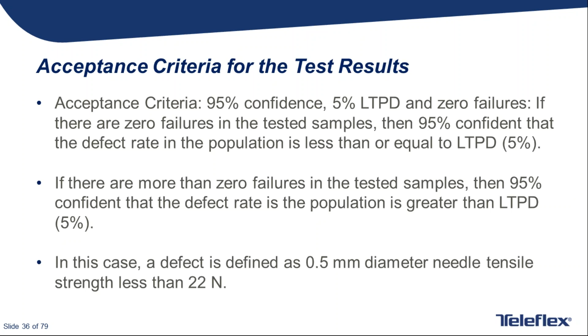So now we're going to turn to the same example, but apply variable testing to it. So it's going to be a little more complicated. For variable testing, we need the same items as for attribute testing, with the addition of power and difference to detect. Acceptance criteria should, of course, be determined prior to testing, but acceptance criteria in this case are not needed to determine the sample size. So that can be kind of counterintuitive to people, so that's an important point to make. We don't need acceptance criteria to begin the testing. Of course, it's best practice to know what your criteria is before the testing, but you don't mathematically need it.